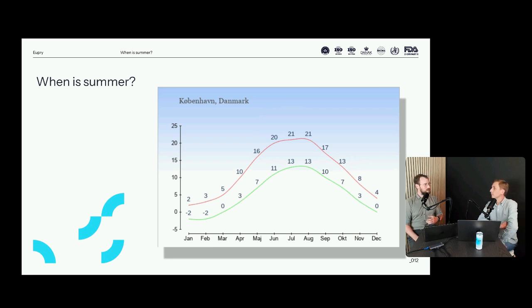The indication is that you need longer mapping periods—the test would run for longer. Where during winter you could be fairly certain it's cold and run the test for a week, the summer mapping might run for 2 or 3 weeks to ensure you get a hot day or two in your study. That might mean your timeline shifts, but it's something to plan for.